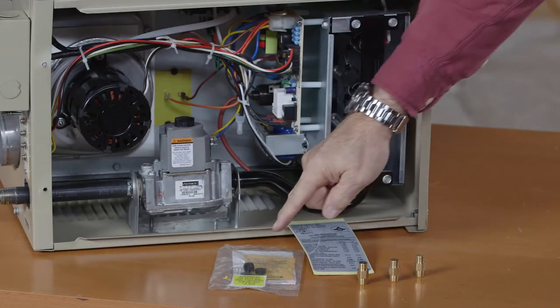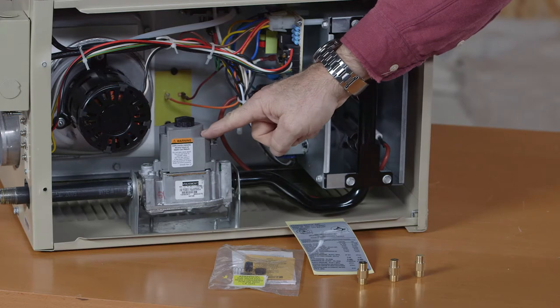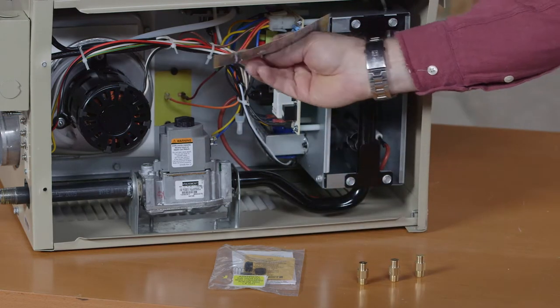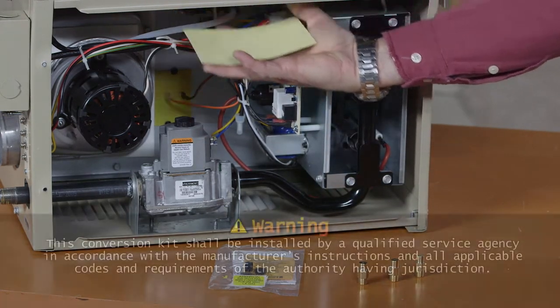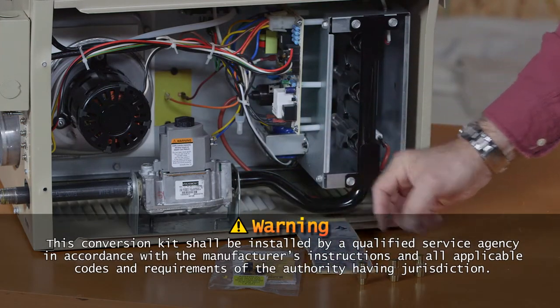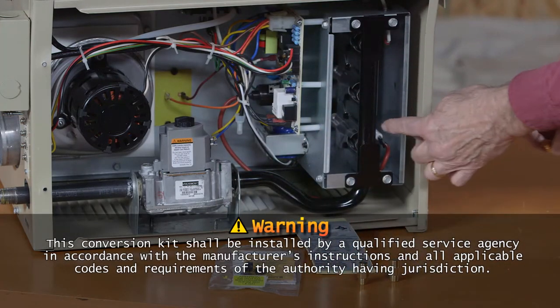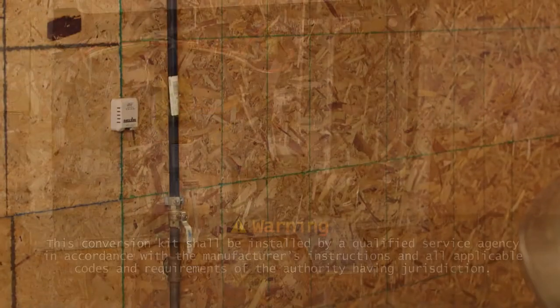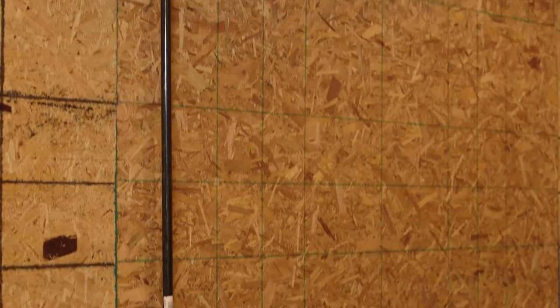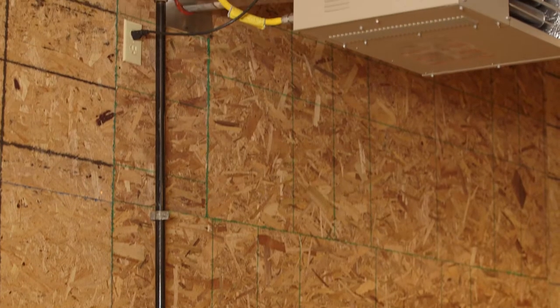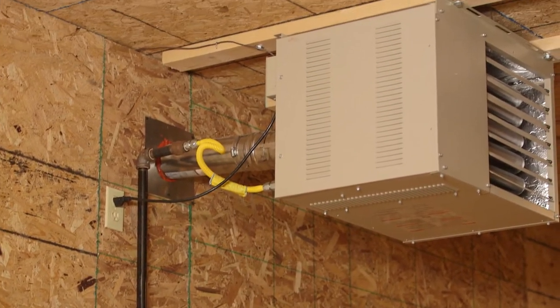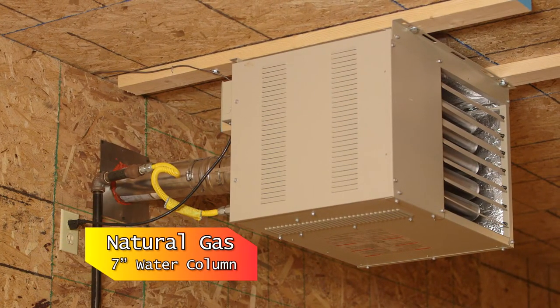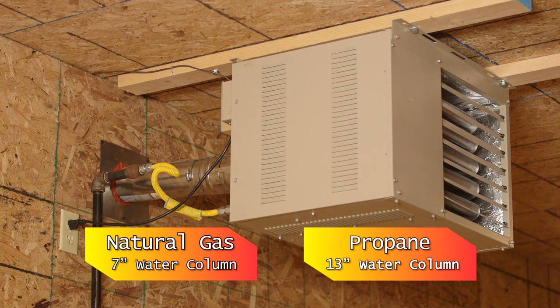All new heaters are configured for natural gas when shipped with the liquid propane conversion kit included. For LP applications, a qualified gas installer must install the LP conversion kit per instructions before installing the heater. The length of the gas supply line from meter to heater will determine the correct pipe size to maintain proper pressure. Line pressure for natural gas should be 7 inch water column. Line pressure for propane should be 13 inch water column.